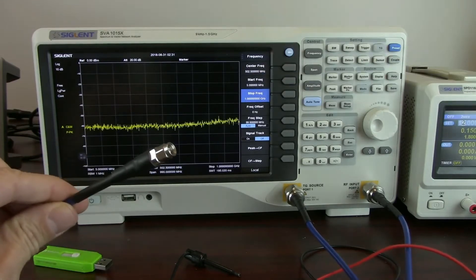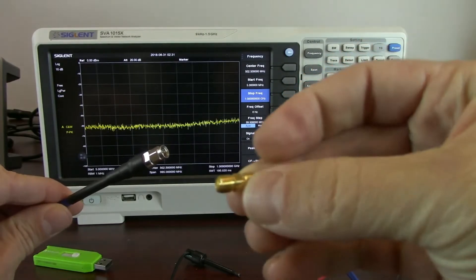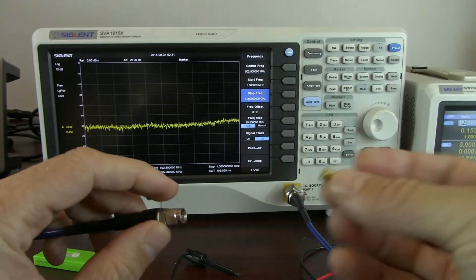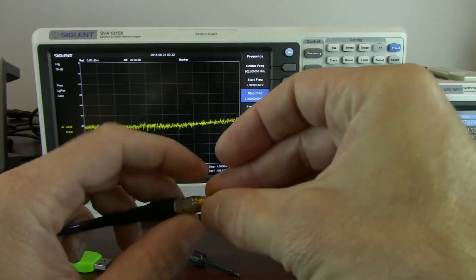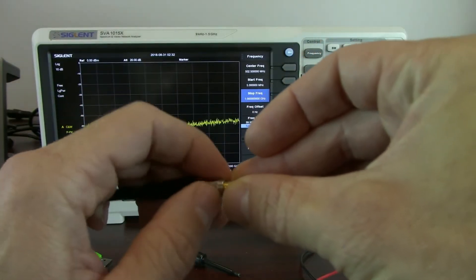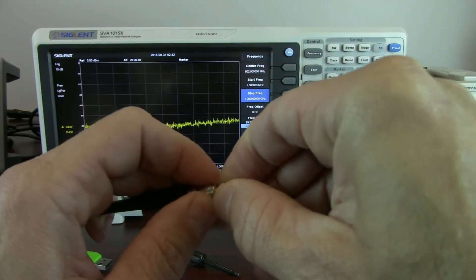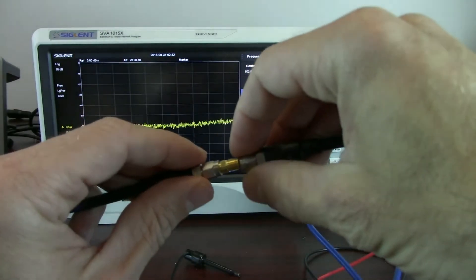We're going to have the two cables, and then we've got a small SMA to SMA through adapter, and we're going to use this in place of the device under test. So we're going to tighten the SMA lug, and note that I'm tightening the hex nut, I'm not spinning the barrel itself, and that actually helps the SMA connections last longer. So you never want to spin the connector, you want to spin the hex nut. And then I'm going to connect the RF input to the other side of the through adapter.